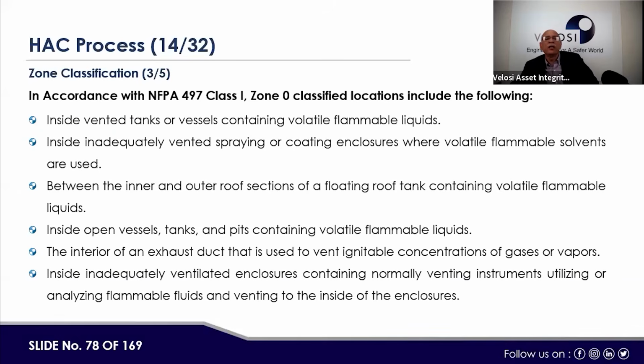Now, in accordance with NFPA 497, Class 1, Zone 0 classified locations include the following. Basically, this is the definition of Class 1, Zone 0. It is the same, but definition-wise we don't need to go through this. This is as per NFPA 497, and NFPA 497 is applicable in the US, not in other areas. We normally follow the definitions of IP-15 or EI-15.